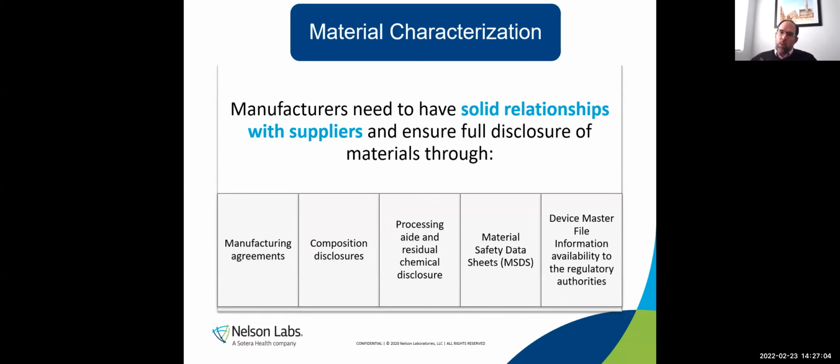NuSil is not the only one that does that. There are a lot of device manufacturers that have device master files. Just a bit of warning though, not all master files are created equal. There's no regulations on what needs to be included in a master file. So some of them like NuSil will have great information with sterilization impacts. Others will just have a cytotoxicity test in them, or maybe a cytotoxicity sensitization irritation. So really ask what's in the master file, what they did to justify it, and line that up with what you need to mitigate the risks.